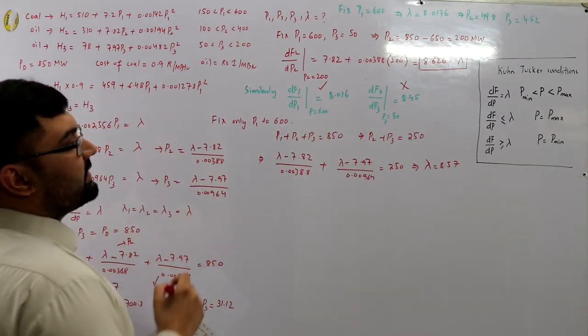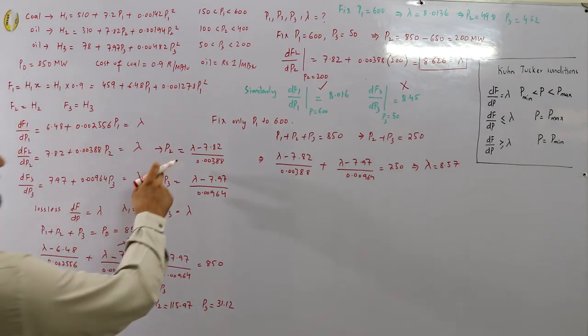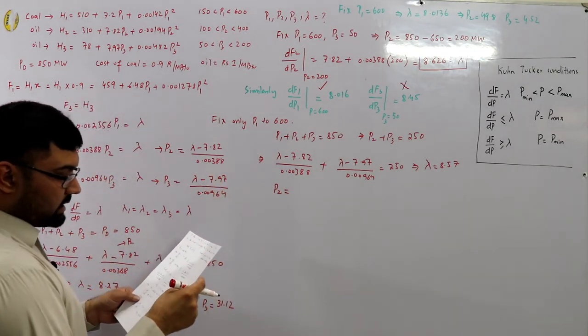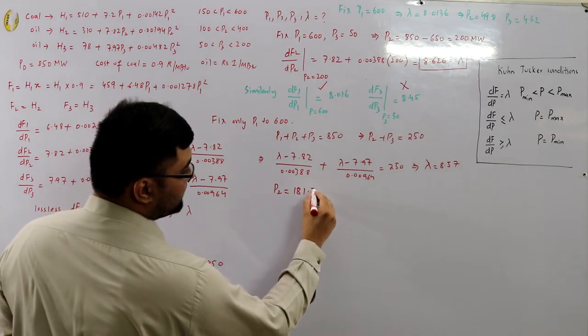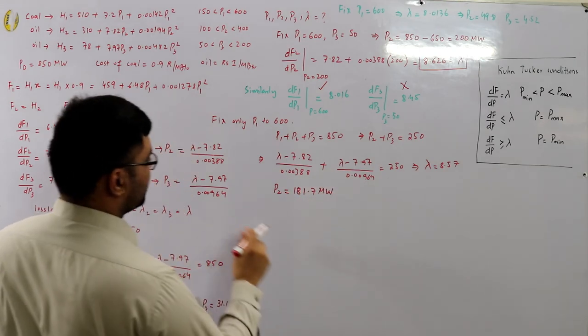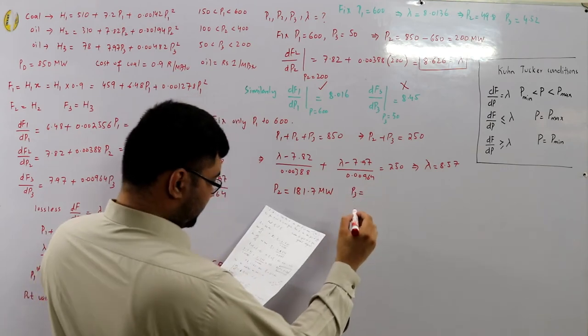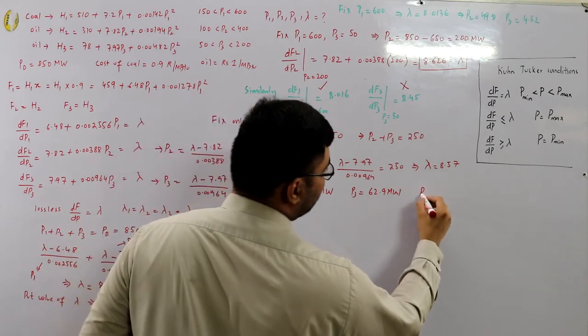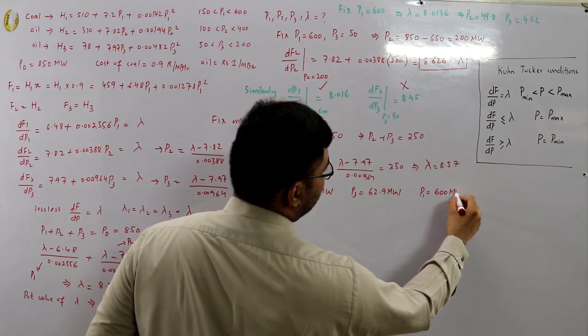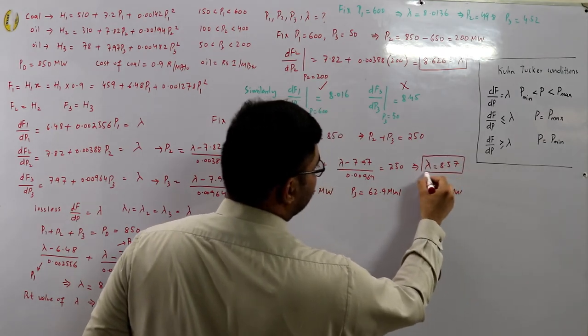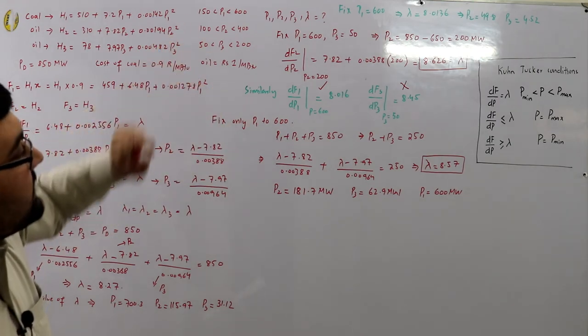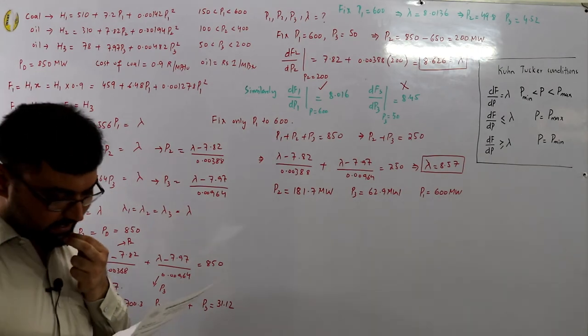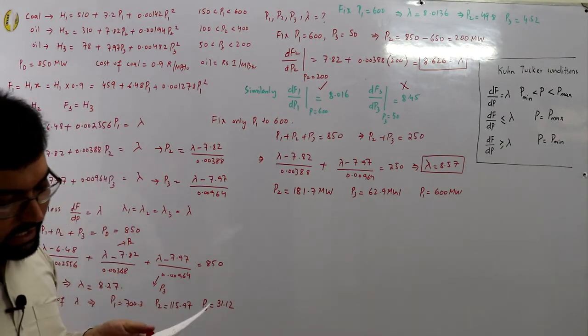With λ = 8.57: p2 = 181.7 MW and p3 = 62.9 MW. Combined with p1 = 600 MW, the total is 844.6 ≈ 850 MW. All three values lie within their respective economic ranges.